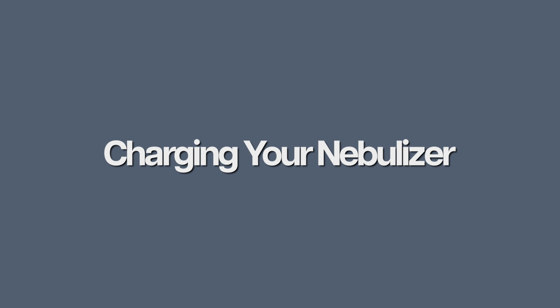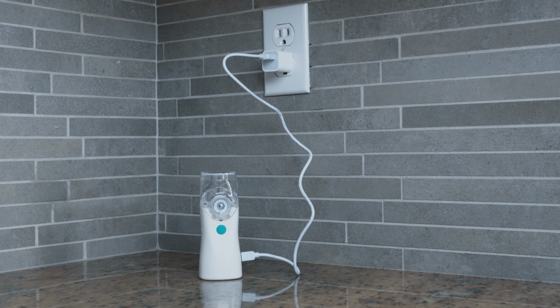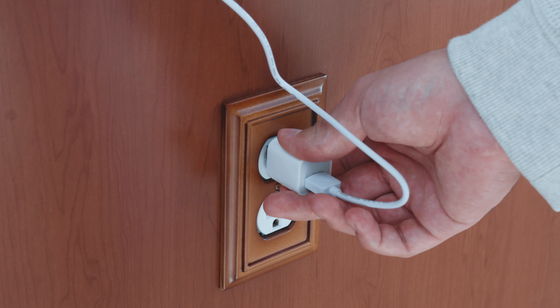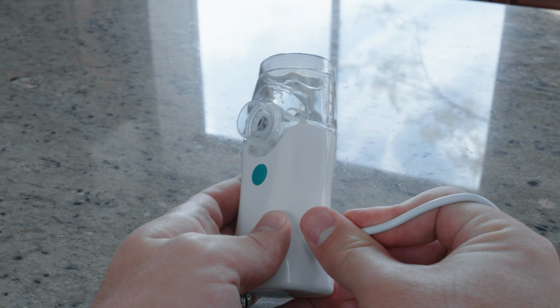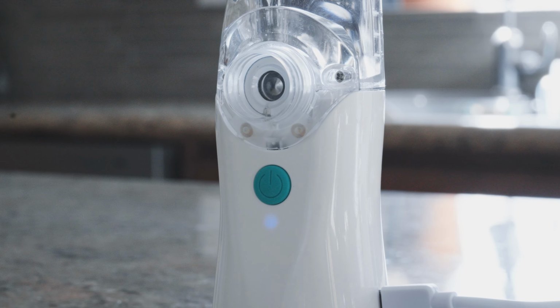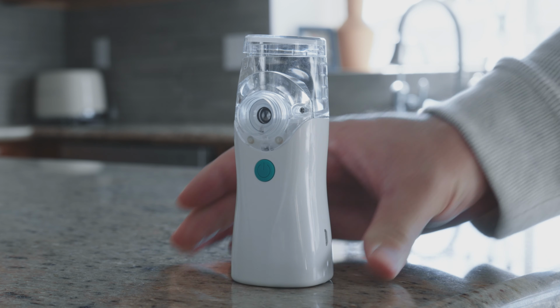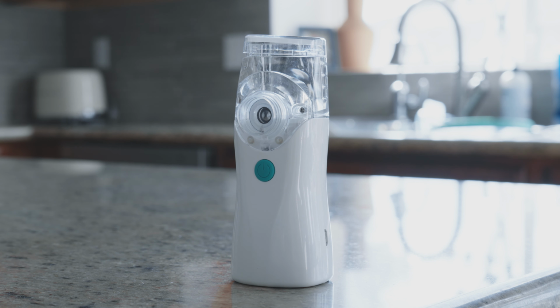Charging your nebulizer. Before your first treatment, make sure to plug in your nebulizer as the battery will arrive without a charge. Plug the USB charging cord into a USB port that has an energy supply. Then plug the other end of the cord into the nebulizer. The light below the power button will blink blue until fully charged, at which point the light will display solid green. Make sure to unplug the nebulizer after the unit is fully charged to maintain the battery's longevity. Even though the battery in your nebulizer will last for 300 cycles, be sure to recharge after every use. We recommend that you make sure to recharge your nebulizer every 6 months, even if you do not use it.